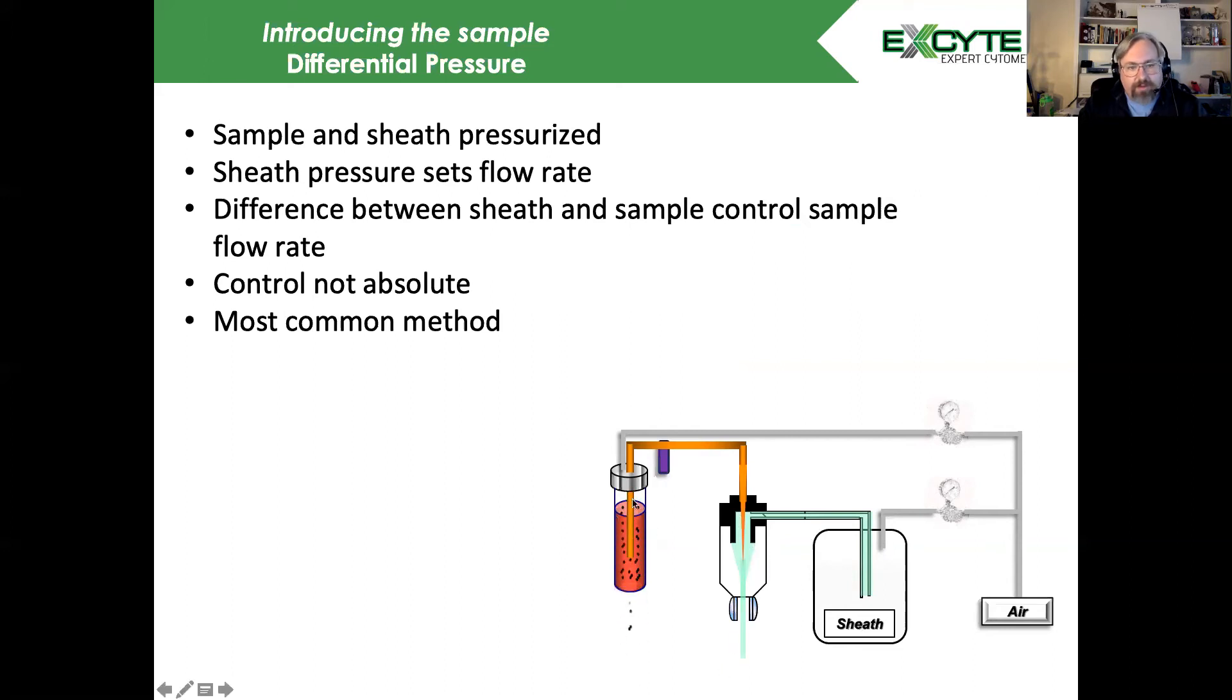When we add our sample to this tube, we've got to make sure we have a good seal here. We have this valve here that's going to let us pressurize this tube, and our cells are going to run through our flow cell contained in the center of the stream. This is one of the most common methods for moving cells through our fluidics pathway, but importantly, its control is not absolute.